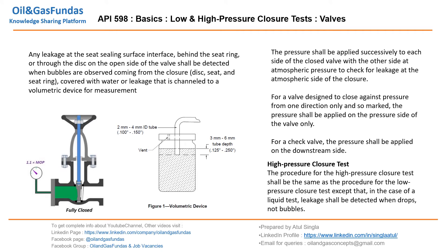We are going to discuss low and high pressure closer tests. Any leakage at the seat sealing surface, behind the seat ring, or through the disc on the open side of the valve shall be detected when bubbles are observed. The valve is closed on one side and open on the other side, and this is connected to a volumetric device where we can detect bubbling or drops to sense the leakage.